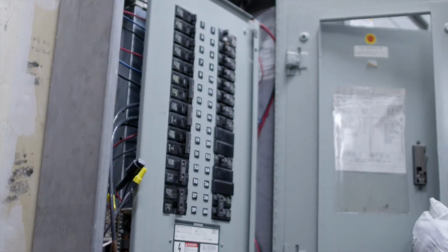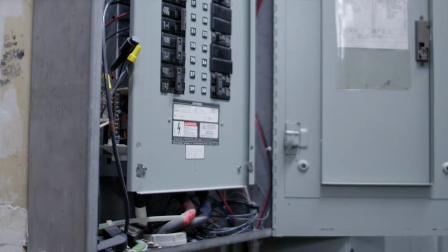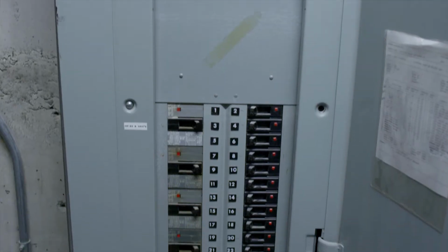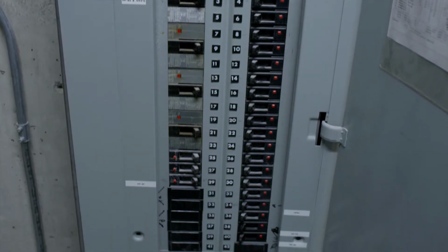The old switchgear was 40-plus years old and never really been tested. Dirt and dust are contaminants, and they actually take away from the integrity of the structure because they're conductive. The arc melts and actually vaporizes the metal in the switchboard, it's so hot. From what we understood, they never operated anything for 10 years.